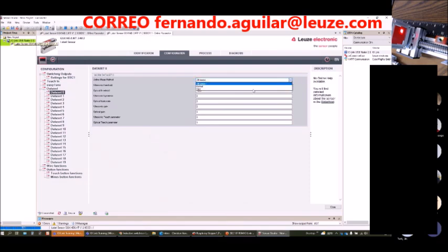You could say, okay, I want this to be optical or ultrasonic, and if you do the automatic teach, the sensor will decide that for you. But here you can force it to one or the other, and then save it using Sensor Studio. These are all parameters that can be set and saved in the IO-Link master. And then if a GSX14 fails and the maintenance team replaces it, they don't need to go in and press all the different keystrokes to get the settings exactly like that failed unit was set.